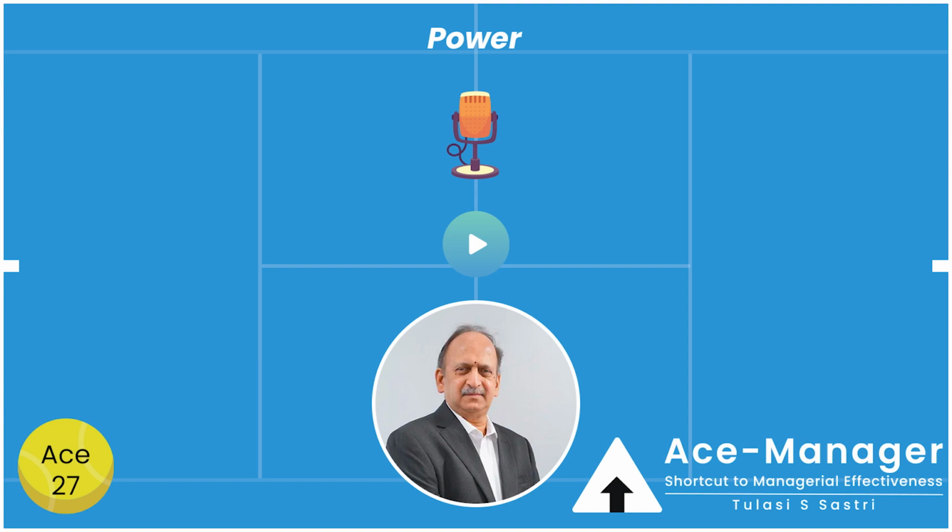The bigger genset of 1000 kVA capacity was new and was more efficient. Its yield was 3.8 units per liter against 1 unit per liter of the smaller sets. This made effective cost per unit of power generated as rupee 1 against 3 rupee 80 paisa of the small set.